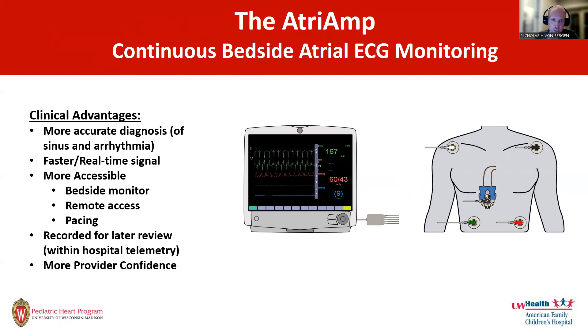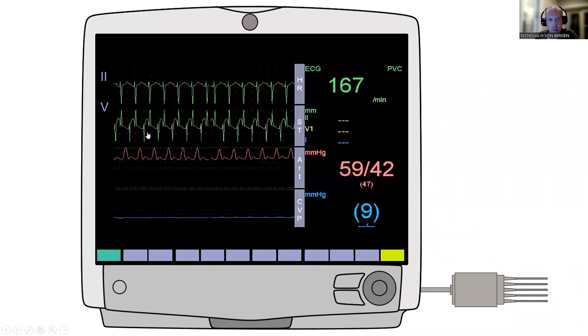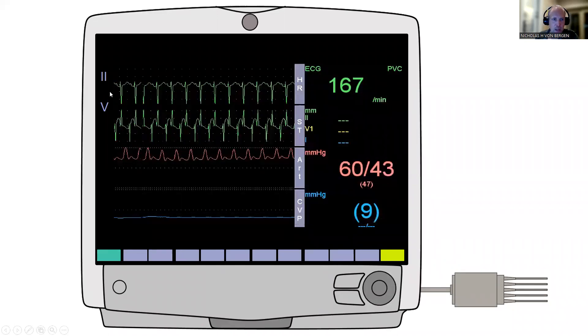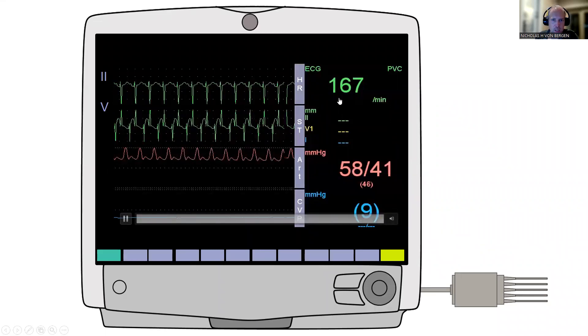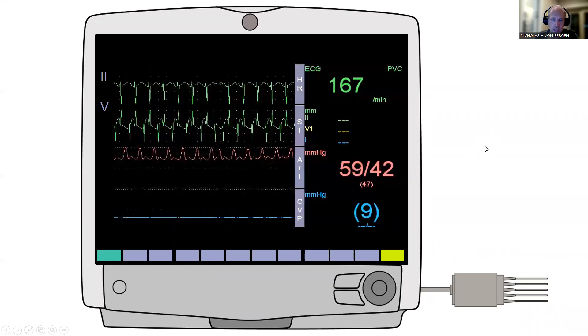We found with research on the AtriAmp that there are improvements in both accuracy and provider competence. Here is an example of the signals from the AtriAmp on the precordial lead. This is a hypoplastic left heart patient. At a lower rate you can see the P waves, but once the heart rate increased into the 170s, those P waves were hidden on the T wave. From across the room, we're always able to see these large atrial signals on the atrial electrogram on the precordial lead — that's the beauty of continuous real-time monitoring.